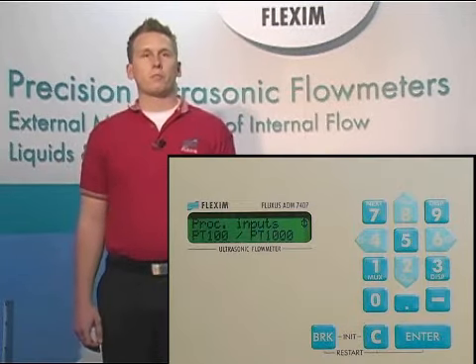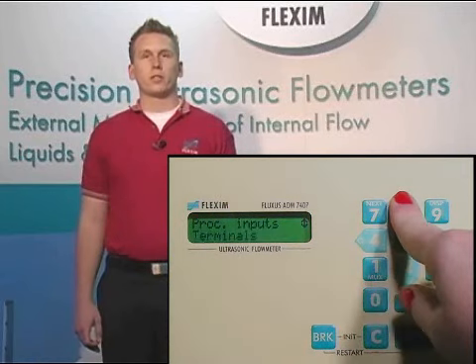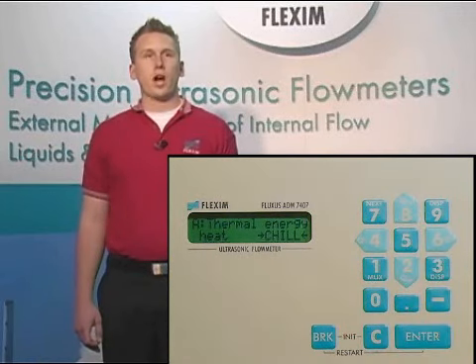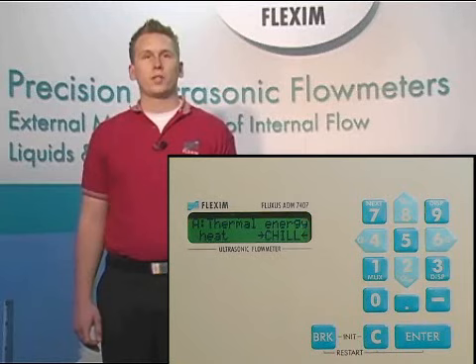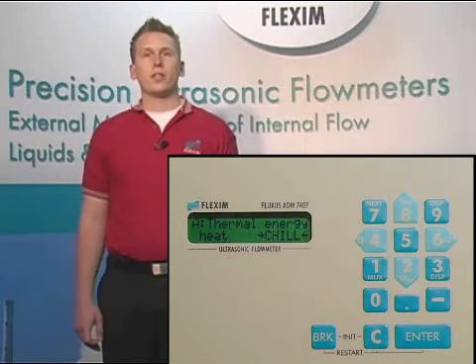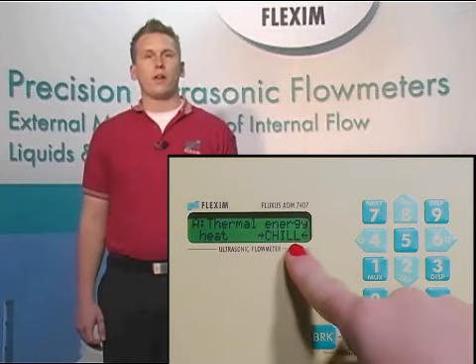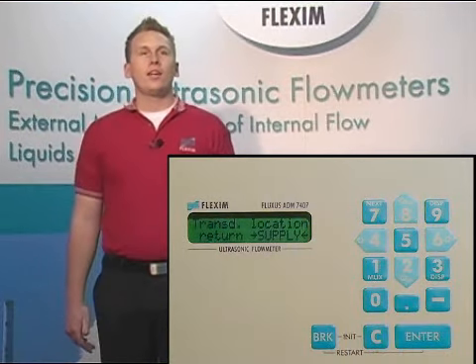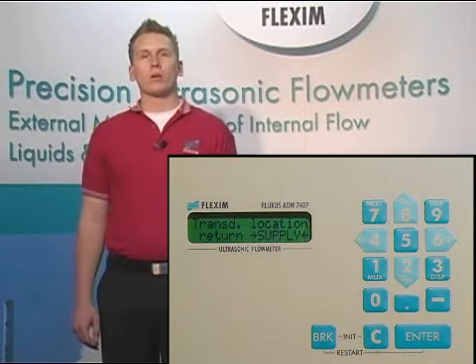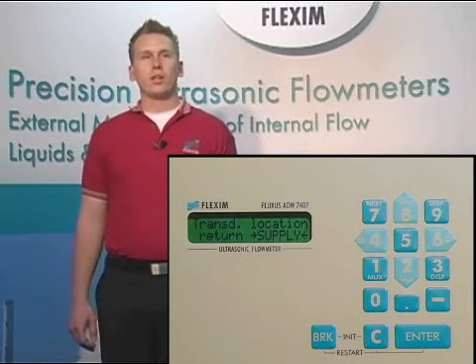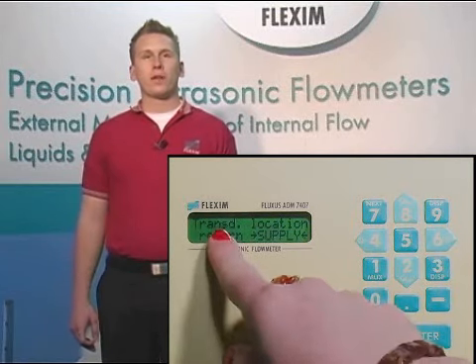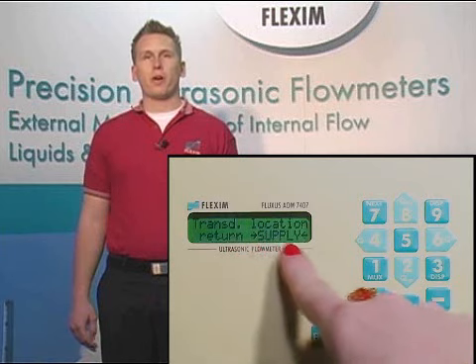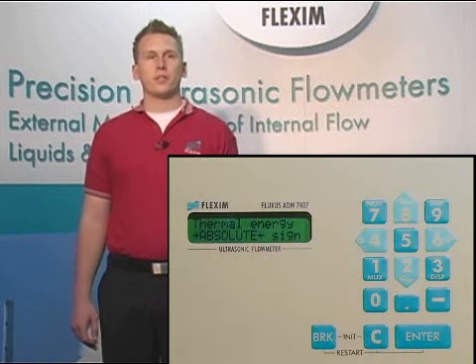Going up one option from PT100, we have thermal energy. Hitting enter here gives us the option of the type of system to set up. We can either use a heating system or chilling system, such as for chilled water. Let's choose chill for now and hit enter. Now we need to choose where we did or are going to mount our transducers, either on the supply line or return line. We generally recommend installing on the supply line, and of course we hit enter to continue.